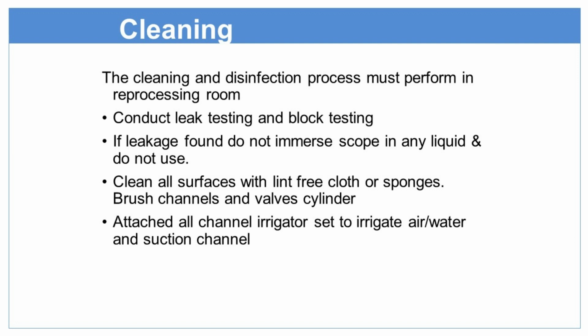Clean all surfaces with a lint-free cloth or a sponge, or we can clean immediately with a gauze piece also. Brush channels, and valve cylinders also need to be cleaned. Attach all channels and irrigator sets to irrigate air, water and suction channels. In cleaning, we must be very careful that all the areas and all the accessories used during the procedure get passed through the cleaning mechanism.